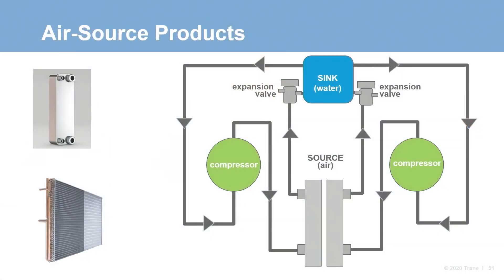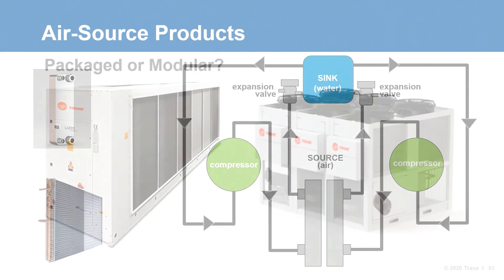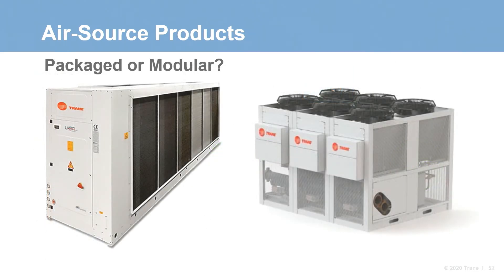So how does the energy contained in the ambient air get transferred to the load water? Pictured here is a generic refrigeration circuit for an air source unit. Ambient air is pulled across the face of the outdoor coil where the energy contained in it is absorbed into the refrigeration circuit. The compressor then adds heat and pressure to the refrigerant, and finally this heat is transferred to the water in the heat exchanger and pumped to the load. Air source heat pumps can come in packaged or modular configurations — let's look at some features of both.